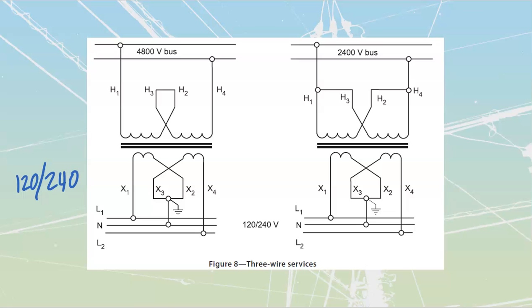If I take a look at it, I see I have my complete 240 volt system connected across the bottom. Let me eliminate some of this over here and some over here, we'll come back to those in a second. On the secondary side I have my 240 volt connection, from here to here to here to here, connected in series to create a 240 volt system. We know line to line we need 240 volts inside a regular three-wire Edison type circuit. Same with this one over here, 240 volts going across from there to there.